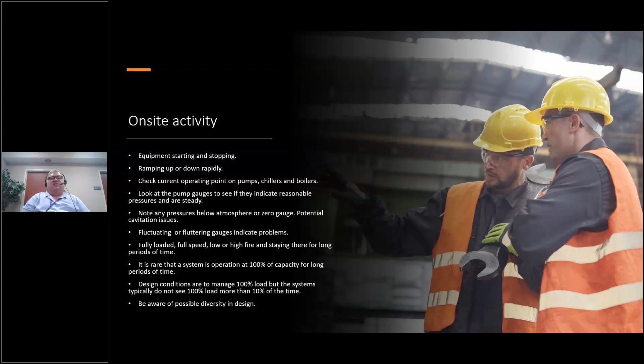Look for contradictions in operation. Variable speed, variable flow, not varying speed or flow. Pumps running at full speed, but not pulling full load, amperage, or horsepower. These drives are wonderful things because you can actually look at them and see, I'm running at 90% of the speed, and I'm only pulling 50% of the amperage or horsepower. Is that okay? Am I able to operate at that point?